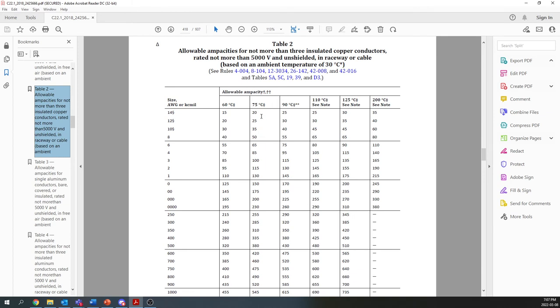So for copper, one load is 75 amps, one load is 50 amps. The first thing we have to look at is what temperature rating we're using. Most all wires that are sold today have an insulation temperature rating of 90 degrees. You're going to see RW90, NMD90, Tech 90, that sort of thing. The 90 means the insulation has a maximum temperature of 90 degrees Celsius. Now, that can be a bit of a misnomer, because while the insulation has a rating of 90 degrees Celsius, the electrical equipment that you're terminating it to, almost in every single case, will have a maximum temperature rating of 75 degrees Celsius.